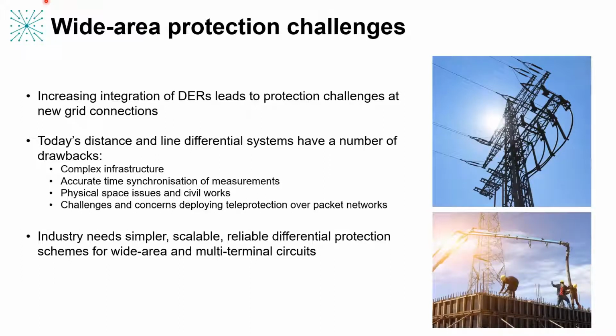So while the industry always wants to deploy robust differential protection because that gives you the kind of gold standard protection of that electrical circuit, there's a clear need for a simplified instrumentation scheme and a scalable instrumentation scheme that allows differential protection to be deployed on wide area, multi-terminal and multi-zone circuits. But it should also retain the reliability of existing methods. So what I'm going to do is move on to explain how Synaptec systems directly address that need.